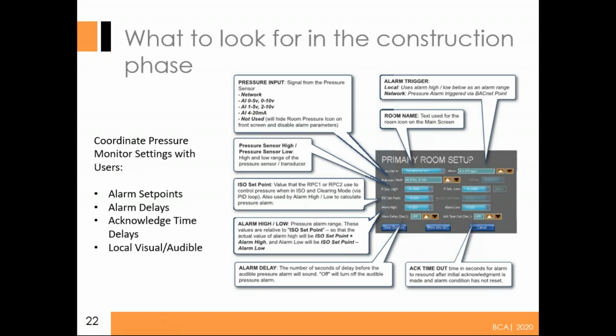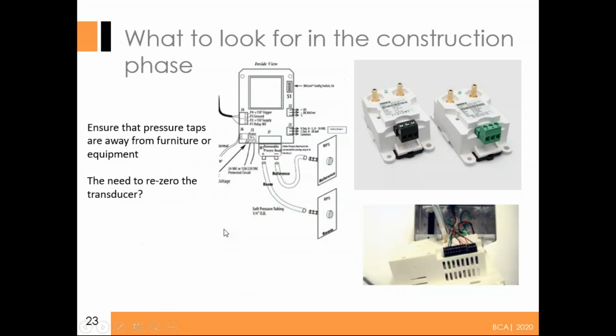Isolation rooms and ORs, their minimum is 0.01 negative or positive. Clean rooms might be 0.05. Just because those are the guides or the codes doesn't necessarily mean that's what the user wants the alarm set to. So work with those alarm settings. And the delays: if a door is going to be open, how long can that panel stay in a warning before it actually sends an alarm out? And whether that alarm is supposed to be audible, because all of these are usually adjustable in the pressure monitors you're seeing nowadays.